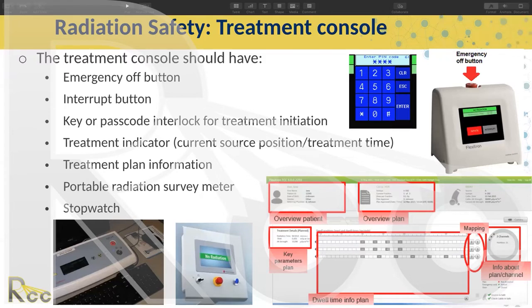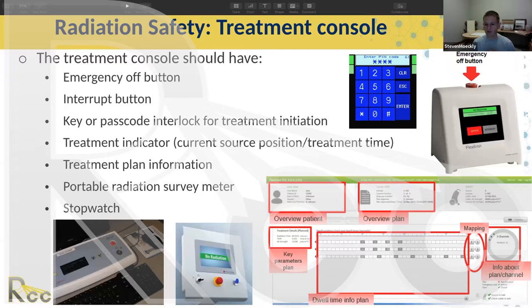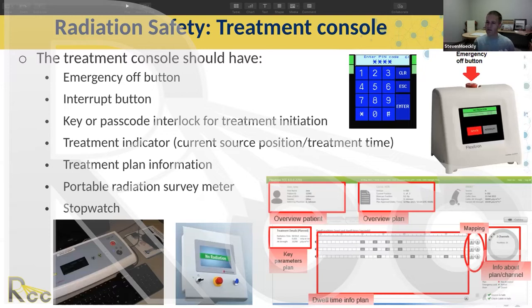The treatment console shows the current source position and treatment time. You need to get well oriented with your machine — how does it display where the source is? If you do have an interrupt, how do you know where it stopped? It's also important to think about what the most common type of problem is with your afterloader, like a stuck source and where it's most likely to get stuck — probably at one of those interfaces. For endobronchial treatments, it can get stuck in many places.